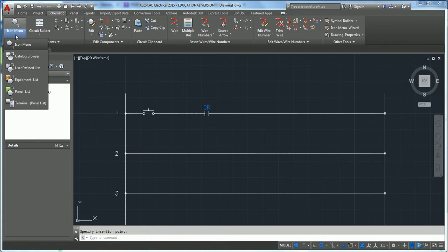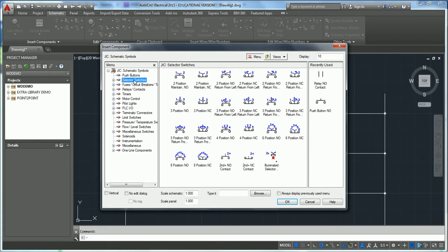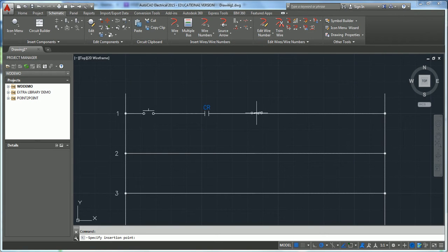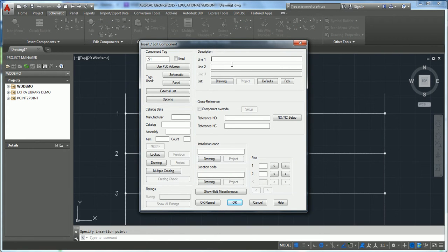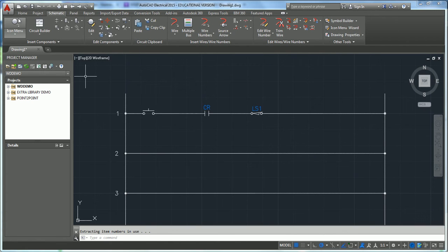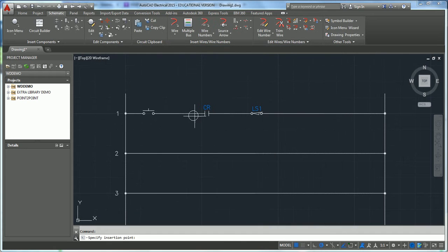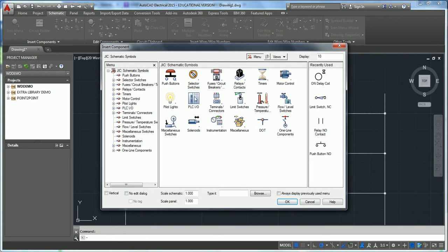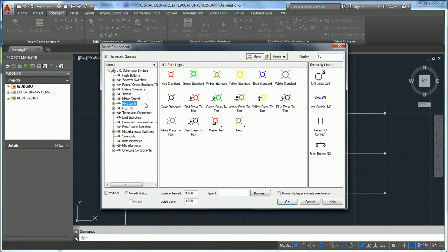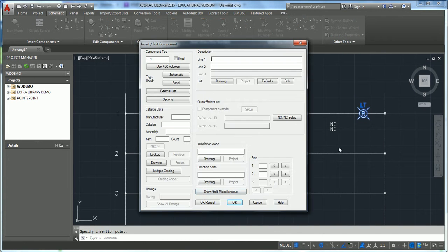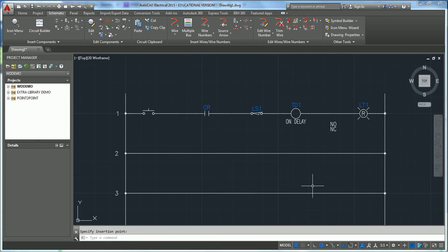Now let's put a limit switch on here. Go to Switches and select a normally closed limit switch — put it right here. Notice how it breaks the wire. There's your tag, there's your description, and you can look up a manufacturer. All of this is going to control a light, so let's find a light. Actually, let's put a timer on there first, then a light. Go find our lights — we're going to do a red light and put it right here. There's my first line: I push the button, it goes through the relay, through the limit switch, through the delay timer, and controls the light.